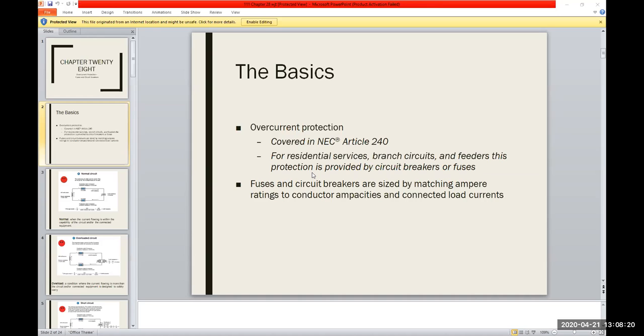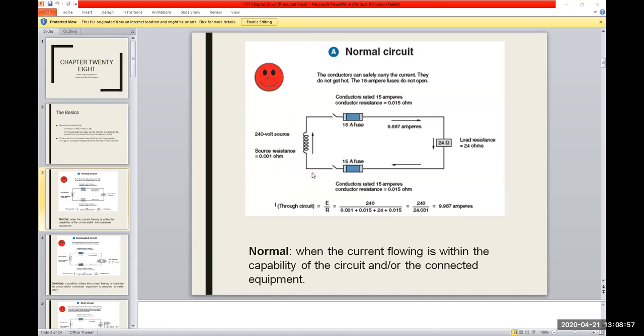Now, in some of the sub panels, for the disconnects for some furnaces or AC units or things outside, they'll have a little sub panel, and you might have fuses in there, and they'll be rated as well. It matches the line. If you had a circuit breaker for 30 amps, you're not going to be putting 40 amp fuses down the line for it, that would just be silly. But it happens. People do crazy stuff. So, a typical deal. A little diagram right here.